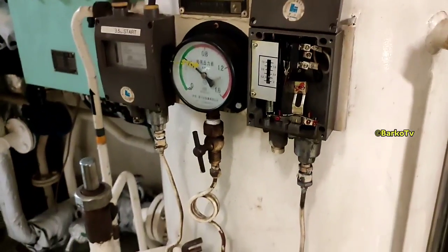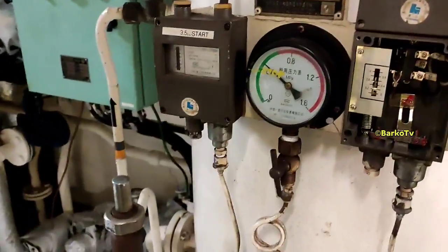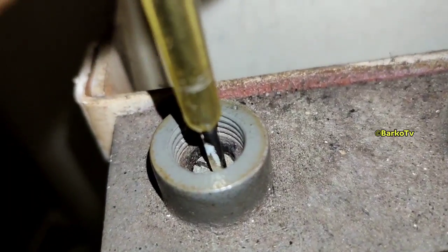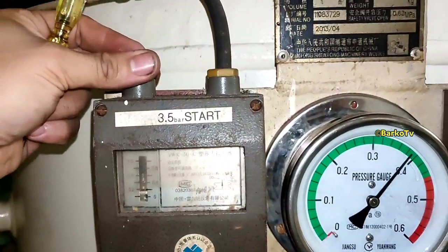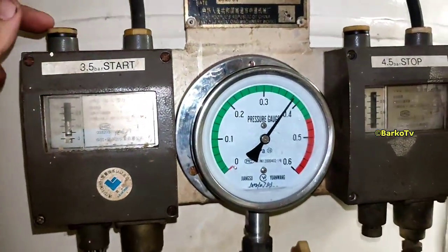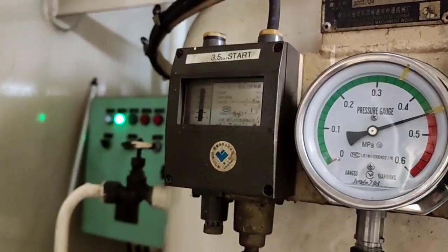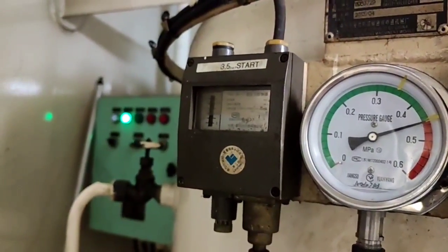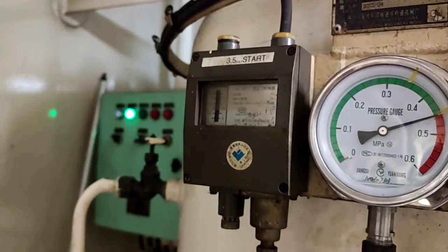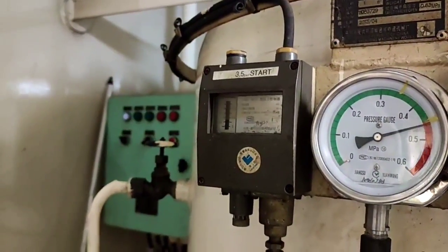That is how to simulate: add air to increase pressure, vent to decrease pressure. For the adjustment, only half a turn on the pressure switch. I already adjusted the start — it was 3.8, so I decreased it to 3.5. I also adjusted the stop to 4.5 bar. When the indicating light turns off, the pump turns off. Thank you very much — I hope you learned from it. Please like, share, and subscribe, and hit the bell for more updates.